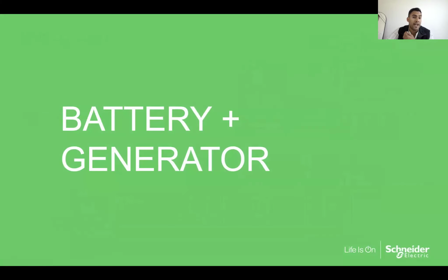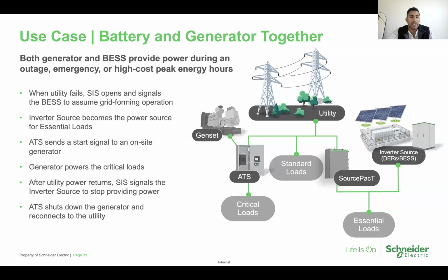So now we're going to go through the battery and generator architecture, and this is something I talked about in prior slides, where we have an ATS and source pack, both independent. In this scenario, we have an ATS there. This could be an existing generator there that you want to have on emergency power for those NEC 700-701 loads. We have your source pack, this automatic interconnection switch, to power your optional standby loads. Again, both of them operate independently, and they provide emergency power, enabling the generator, and also an energy storage system, for an emergency scenario.